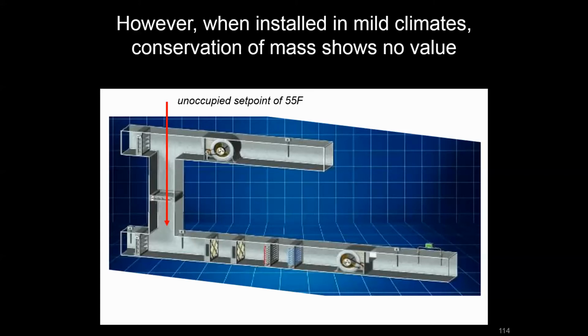control system that has a lower limit so that when zones get below 55 degrees, the unit will activate and it'll have some unoccupied heating mode. So at the lowest case, we would expect about 55-degree air to be coming from the return. And maybe say when that happens, let's say we happen to be at our design low. In this case, we'll throw out a number for somewhere like Central California at about 38 degrees outside. So we would hope that in that unoccupied mode that our outside air damper stays closed, because we don't need ventilation, we just need airflow to accommodate that heating of the zones.